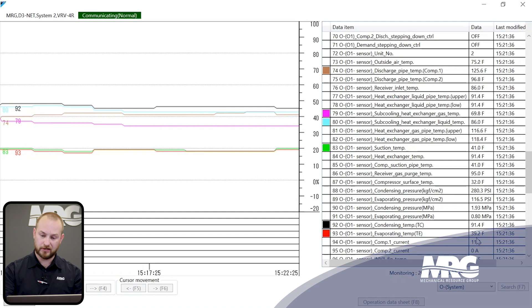What you're doing is going through and looking at all the indoor units, making sure they're all reading correctly — if one is out of range, that's where you start troubleshooting. The best approach when you know you have a liquid refrigerant problem is to put the system in full cool mode with every unit on, then one by one switch indoor units to fan mode. In fan mode, the expansion valve should go to zero pulses — you should achieve positive shutoff with zero flow through that coil. Give it about 10 minutes to let heat absorb into the coil. If temperatures stay down near the saturated evaporator temp rather than rising to return air temperature, that's a definite indication that the EEV is bleeding by.